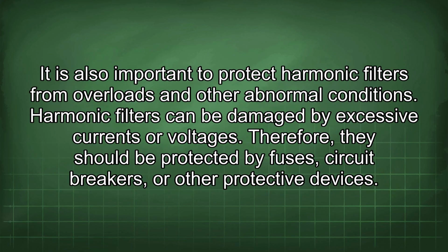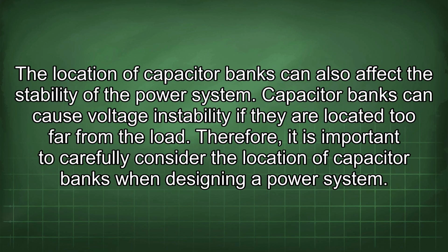It is also important to protect harmonic filters from overloads and other abnormal conditions. Harmonic filters can be damaged by excessive currents or voltages. Therefore, they should be protected by fuses, circuit breakers, or other protective devices. The location of capacitor banks can also affect the stability of the power system. Capacitor banks can cause voltage instability if they are located too far from the load. Therefore, it is important to carefully consider the location of capacitor banks when designing a power system.